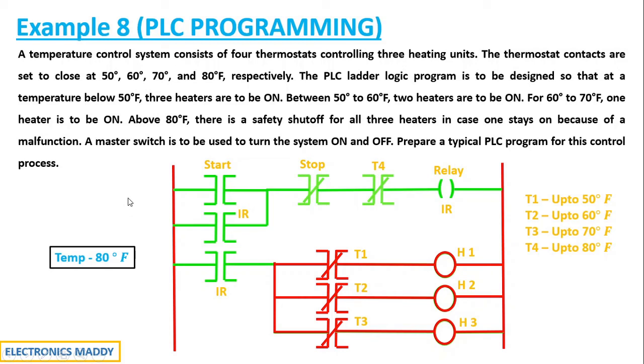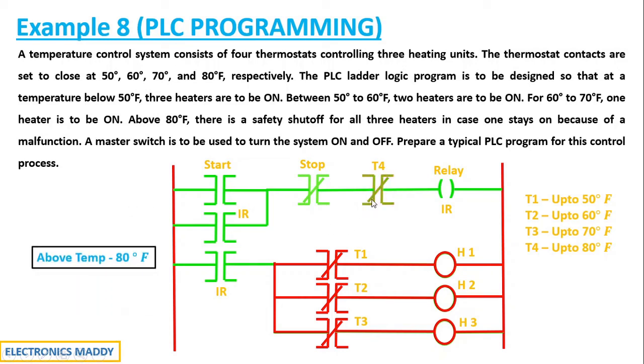Beyond 80°F, T4 should be turned on. When it is turned on, it acts as an open circuit because these are normally closed contacts. Consequently, no current flows through this path. The relay gets de-energized; since the same IR address is used, if this goes to zero, this will go to zero and the entire unit will be turned off.